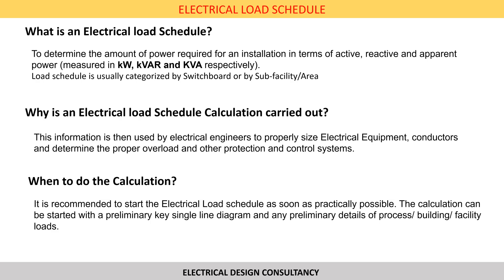So what is an electrical load schedule? An electrical load schedule can be defined as a document that embodies the total electrical load within the plant. It is used to determine the amount of power required for an installation in terms of active, reactive and apparent power, measured in kilowatts, kVAR and kVA respectively. A load schedule is usually categorized by the switchboard or by sub-facility or area.